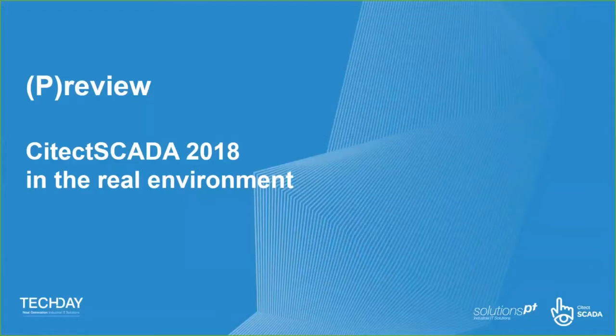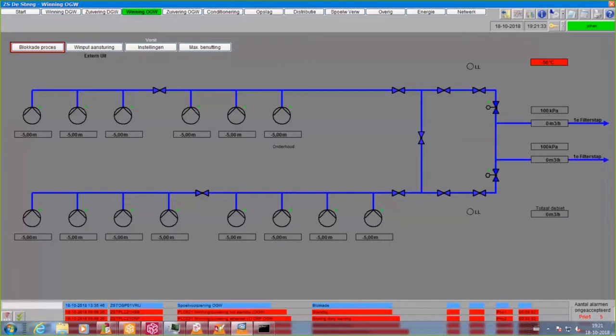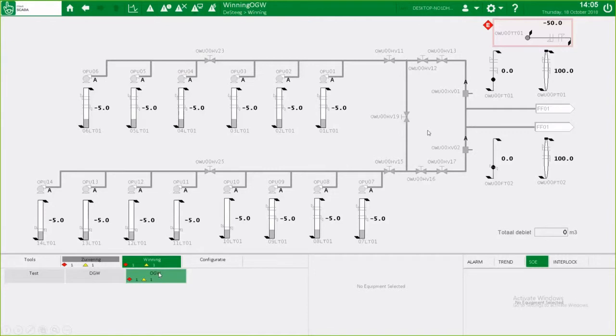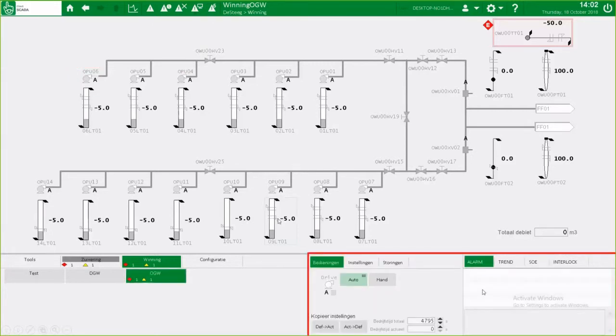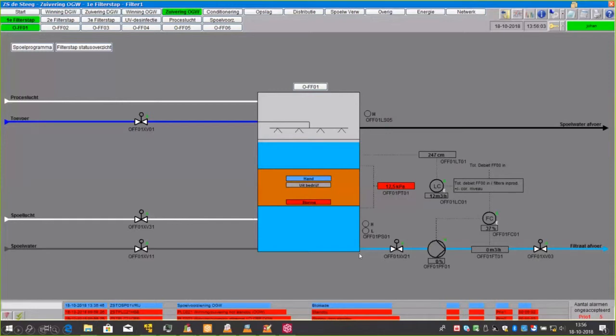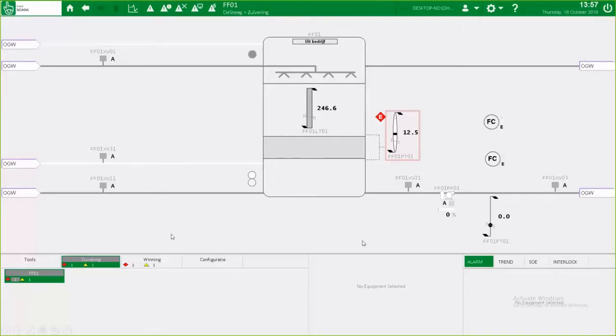Let's take a look at a project that was recently upgraded in the Netherlands. This is the previous mimic of their booster stations, and what was provided in 2018 was this new mimic — selecting that pump updates the face plate, alarm, and trend information areas. Note that this face plate is slightly different from those seen before; even though CITECT provides face plates out of the box, it does allow you to customize and configure them more specifically to your application. Looking at the filtration mimic: the old look versus the new look — straight away it is very easy on the operator's eye and the information being displayed is very clear.